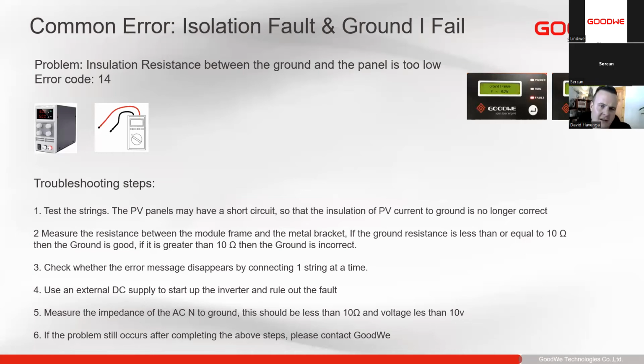But if you just have a regular insulation resistance tester, normally you don't always want to inject, especially if you have a small string of only 200 volts, you don't inject 600 or 1000 volts through your modules. You'll disconnect the modules, connect your cables, and do your insulation resistance test. So that will run the current through the cable, and you measure from one of your cables to ground, and then you'll see if the insulation is correct or not. So a lot of installers, and bigger installers, EPCs, will also do these kinds of tests on commissioning before even connecting to the inverter, to make sure that everything is 100%.